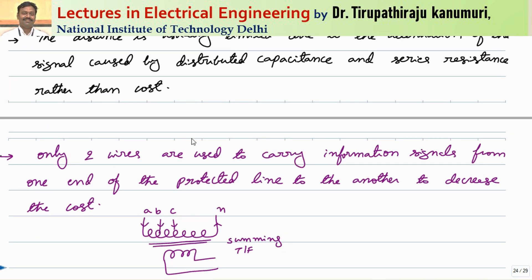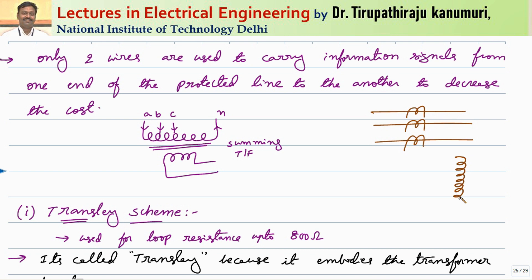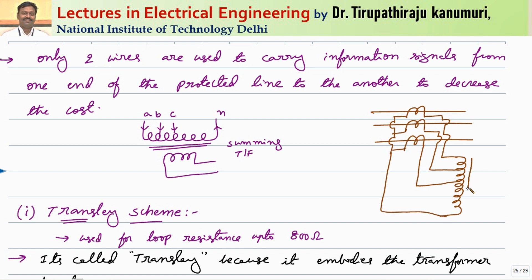The distance is usually limited to between 15 to 30 kilometers due to signal attenuation caused by distributed capacitance and series resistance. To carry complete three-phase information over only two wires, we use a summing transformer. The secondary of the CTs are connected to this transformer. The primary winding is connected so that R, Y, B phase currents are applied, and depending on the net value of current, net flux is produced in the core, which links with the secondary and induces EMF on the secondary side.